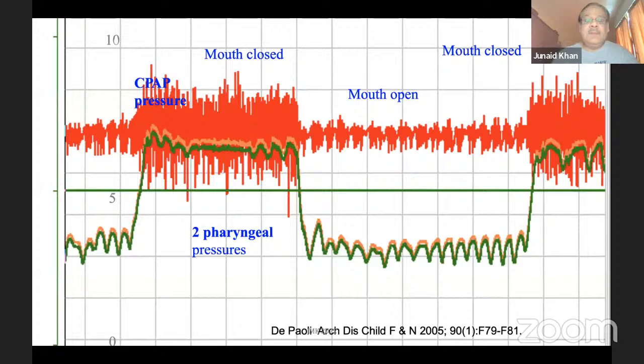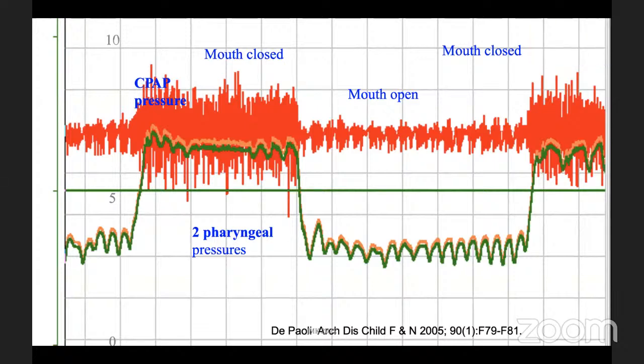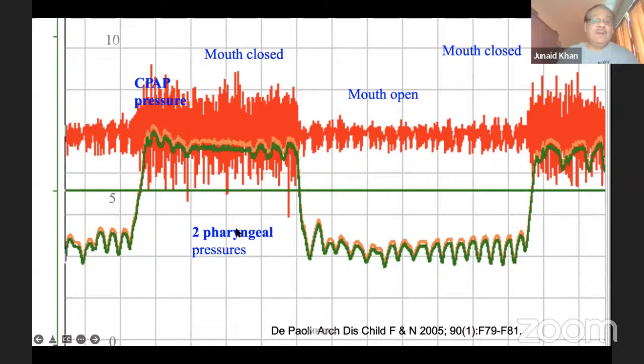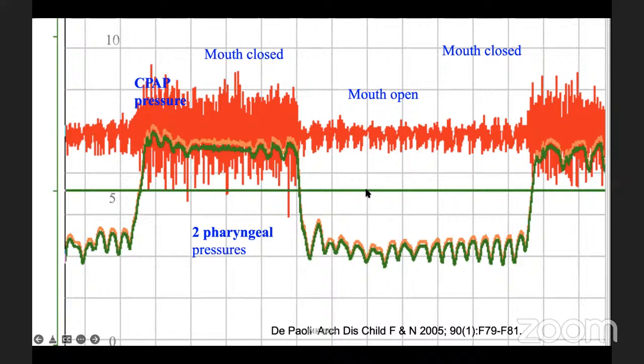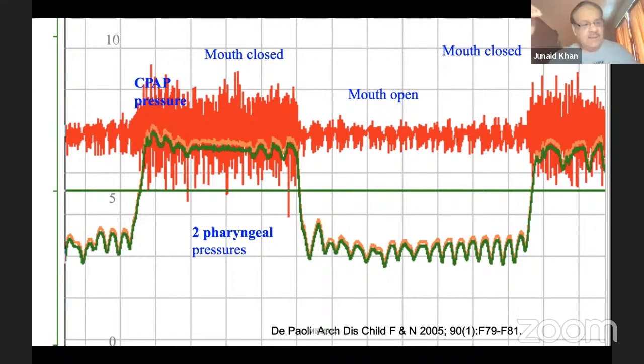The problem with the bubble CPAP or any form of CPAP is the pressure control when the mouth opens and when the mouth closes. So look at this, the two pressures, the pharyngeal pressure and the CPAP pressure itself. If you close the mouth, the pressure goes up. If you open the mouth, the pressure goes down. It is no rocket science. That's why sometimes in a very small baby, they put a band, but do not put a very tight band because it can cause pneumothorax. It will increase the pressure too much. So if the baby is doing fine on CPAP, there is no need for that tie or band around the face. But if not doing very well, then you can put it to increase the pressure which we are providing.